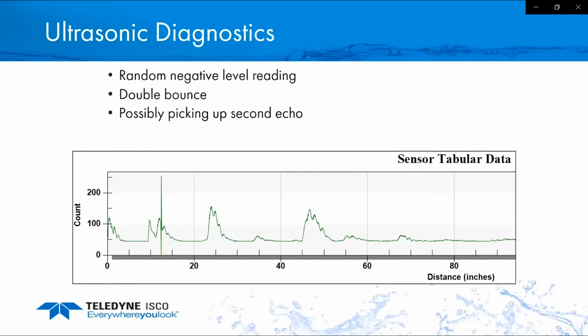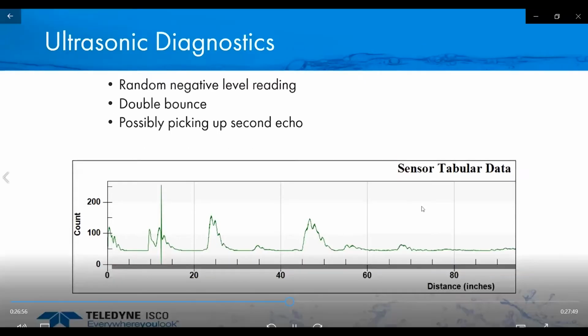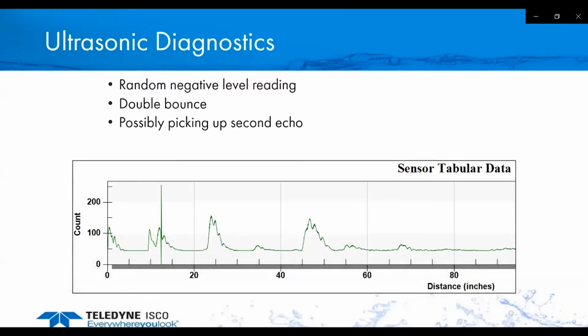The way to overcome that is you should have the ability to adjust your blanking distance, so you want to set your minimum and maximum blanking. In this case, if we had set the blanking at 15 inches and 50 inches, it would isolate this area right here and pick up just a good reading, and then throw out any additional echoes or bumps after that. The cause of this could be that it's hitting the top of the flume wall, or it could be debris going through there or foam, and that's what's causing it to pick up secondary echoes. But hopefully the flowmeter you have is programmed smartly enough that you can set the blanking to correct that problem.